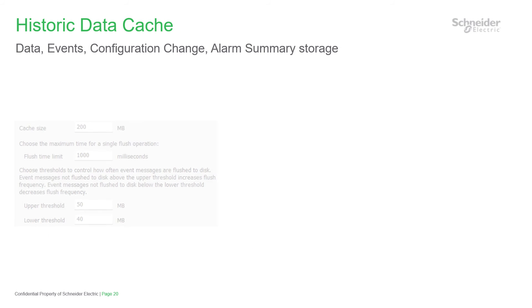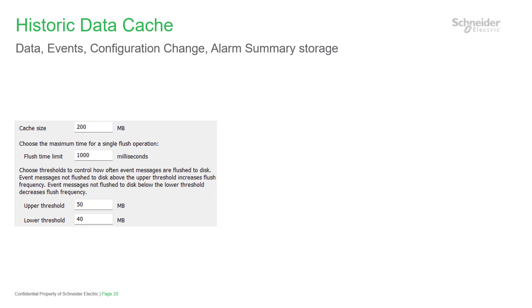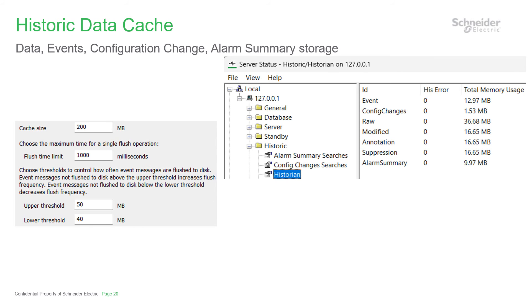A review of historian settings and performance wouldn't be complete without discussing the historic cache settings. Taking cache size first, this setting allows the server to retain history for faster searches. The cache contains both writable and unchanged data. And if memory is available, you can increase this for performance, which depends very much on the type of queries used and the writable data in the cache. Check usage in the cache columns in the server status page.